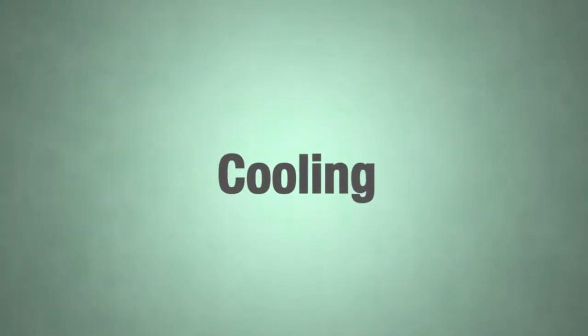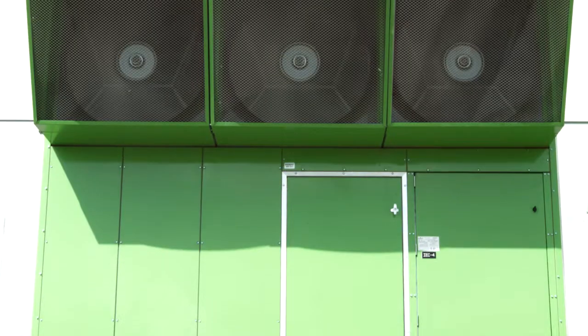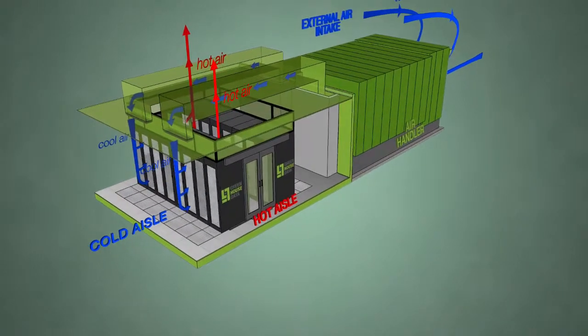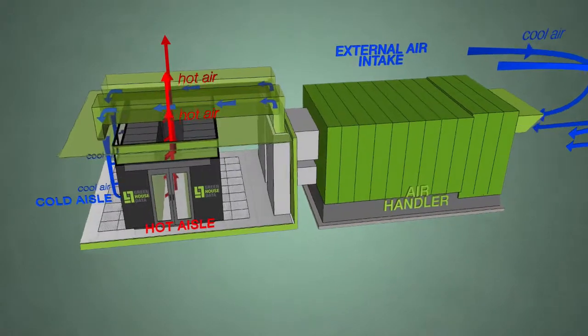We went with an indirect evaporative cooling system because it allowed us to really leverage the outside ambient air here in Cheyenne. Greenhouse Data employs a cold aisle, hot aisle containment system and we use a strong, secure polycarbonate heat containment system combined with an APC insulated door and we're only seeing about 3% bleed out in these pods.